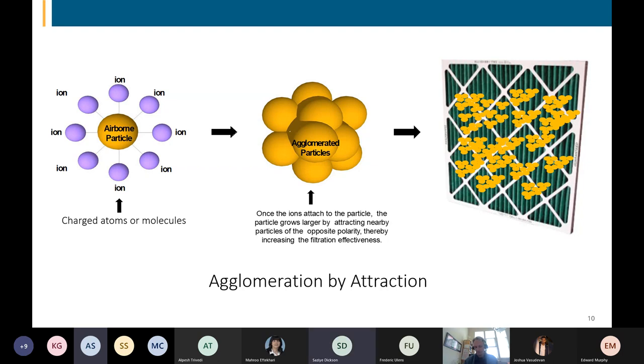Yes, we have two questions. The first one is, does the ionization device continually monitor ozone levels in the space? How is the secondary production of ozone by ions combining with oxygen? Okay, so typically most ionization technologies themselves do no monitoring unless you install ancillary monitoring equipment in the space to be able to do that for you or for your client.